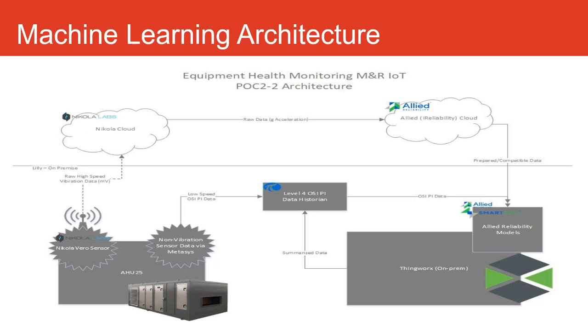For example, I may have 26 different Metasys points going into OSI Pi for all those attributes - pressure, temperature, flow, humidity - plus vibration and temperature data. Now those pieces come together to give a holistic asset health picture. When I move to the machine learning aspect of this, I can say: if my vibration is above 0.375 inches per second, and I see a VFD percentage over 90%, or a damper that's fully wide open, that should trigger me to investigate.